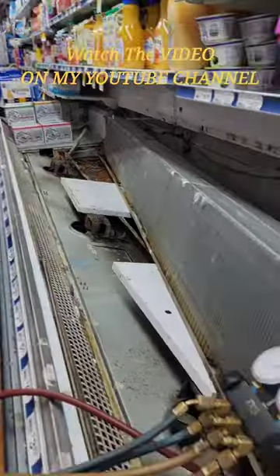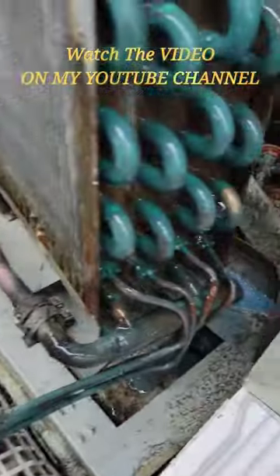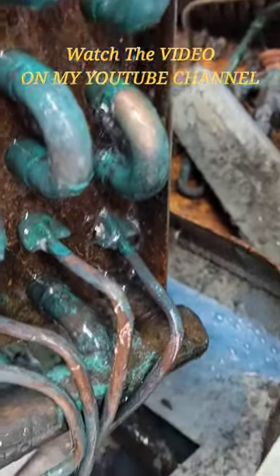You can kind of see what we're doing. I've been spraying everything in there as best as possible. We've got her torn out, put a stub on it, got a plug here on the flare fitting — we've got a leaker. This is gonna be on one of my videos. It's only a hundred pounds of pressure, that's definitely not doing well.